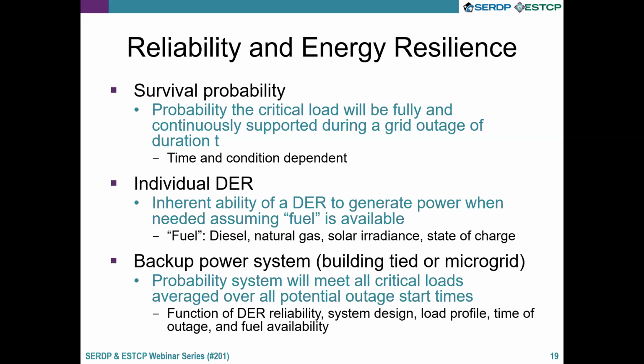Backup power systems can be as simple as one or two generators tied to an individual building to support its critical load, or, more commonly and of interest for this series of talks, configured in a network as a microgrid. What we're really interested in is whether the system, building-tied or complex microgrid, will meet all the critical loads for the required duration, independent of when the outage started—whether the first hour of January 1st or the last hour of December 31st. This depends on DER reliabilities, which have generally been ignored in previous analyses, as well as microgrid design, critical load profile, time of outage, and fuel availability.